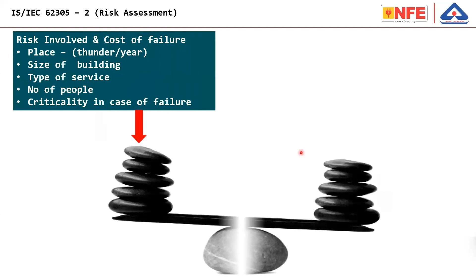It was also claimed that lightning protection, risk assessment and risk management. There is a claim going on in the media which says that risk assessment as per the Indian standard is wrong, because sometimes the people who are talking don't understand the difference between risk assessment and risk management. What is explained in the standard is risk assessment of a building, not an open area. It is not applicable for an open area. It is not applicable for a traveling vehicle, a vehicle which is moving. It is applicable for a fixed structure. Now, for that, how to make a risk assessment?